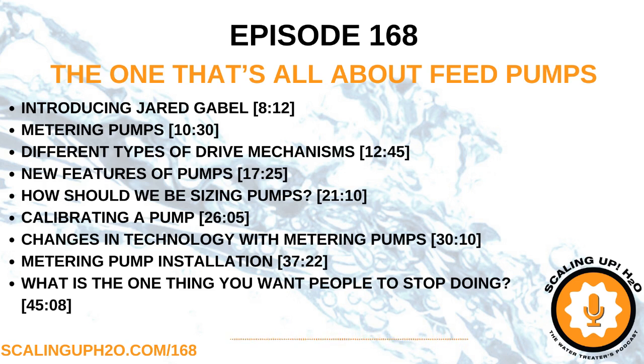Jared, what do you think the average life expectancy is of a metering pump? That is a good question. Depending on the environment you're in, you should have a pump that lasts 10, 20 years. The reason I say that is because there are really only a couple of things that you're managing: following the manufacturer's instructions on ambient temperature conditions around the pump, because again, nowadays they're like little computers. But as long as we're updating the check valves, diaphragms, or any of the wet end pieces that are the change out parts, and you're keeping them up to date and maintained, the pump should last a long time.